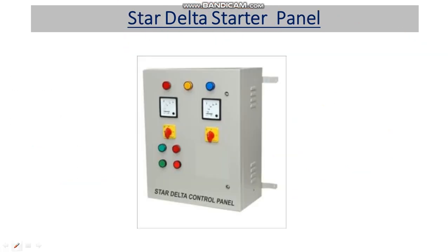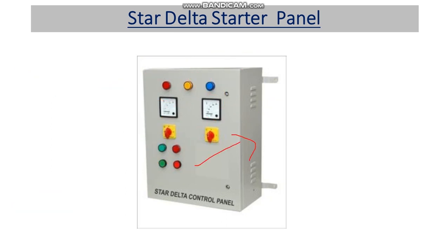Now let's look at the star delta starter panel. It has push buttons for start and stop, three-phase monitoring indicators for R, Y, B phases, an ammeter to measure current of each phase, a voltmeter to measure voltage, and an on/off indicator to monitor whether the motor is running or stopped. Internally the panel has three contactors — one main, one star, and one delta — plus an MCB, an OLR, and an on-delay timer.